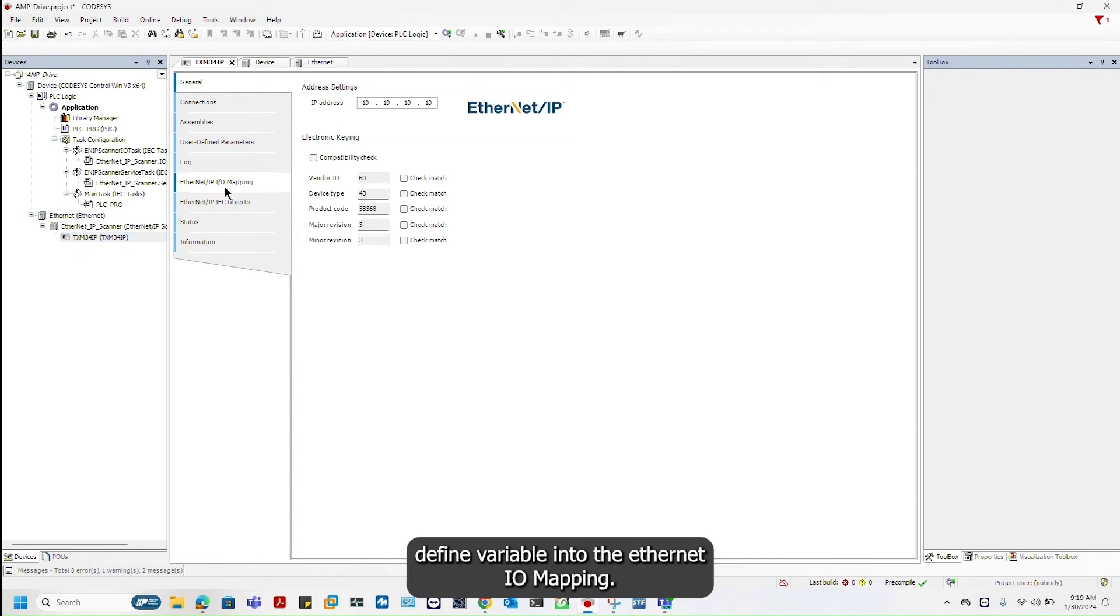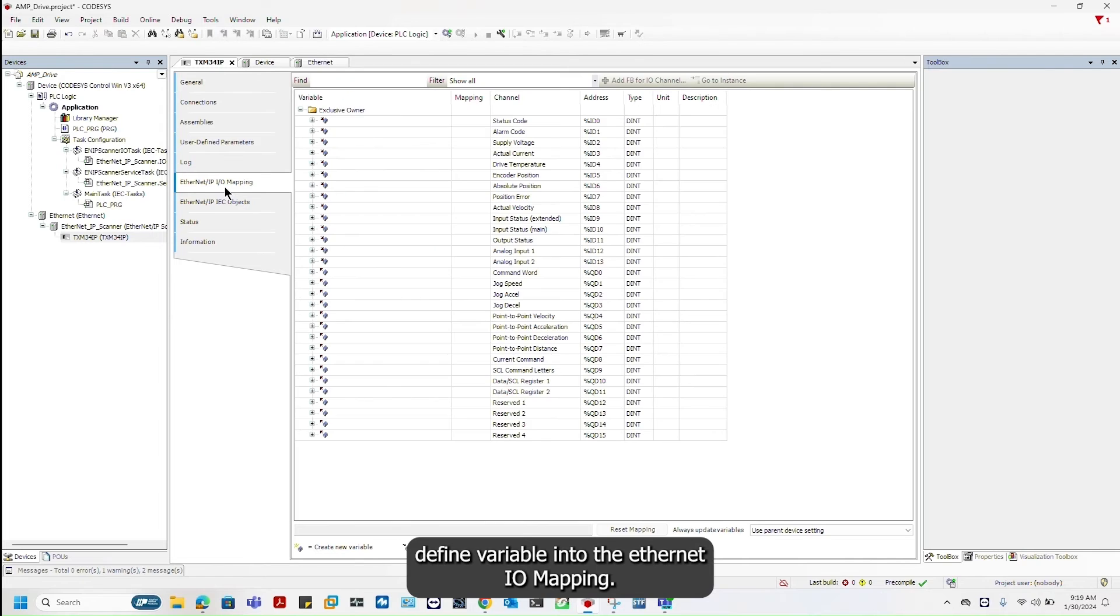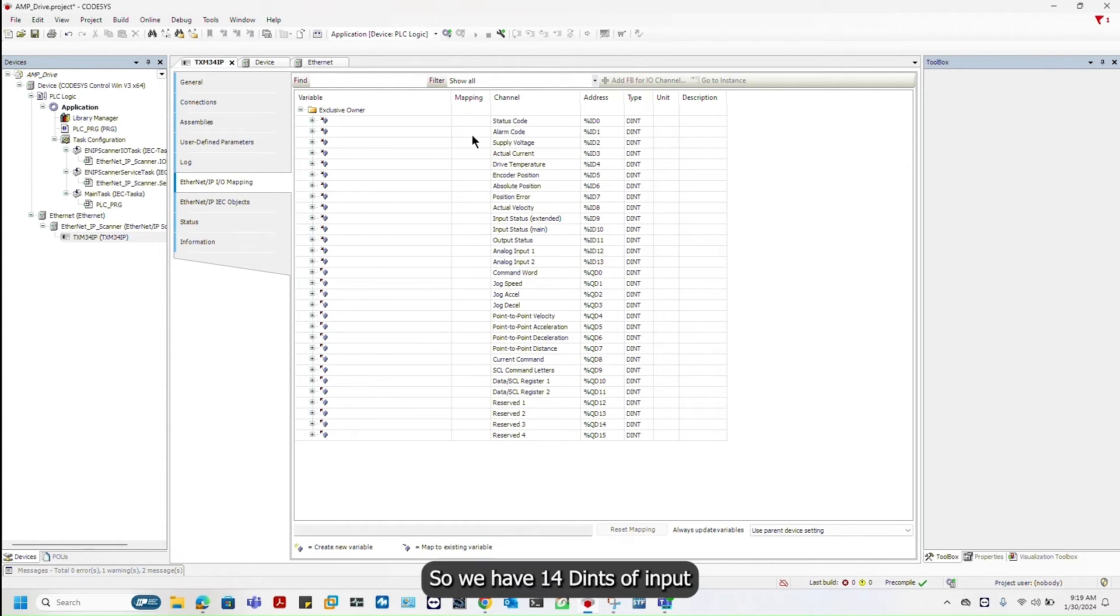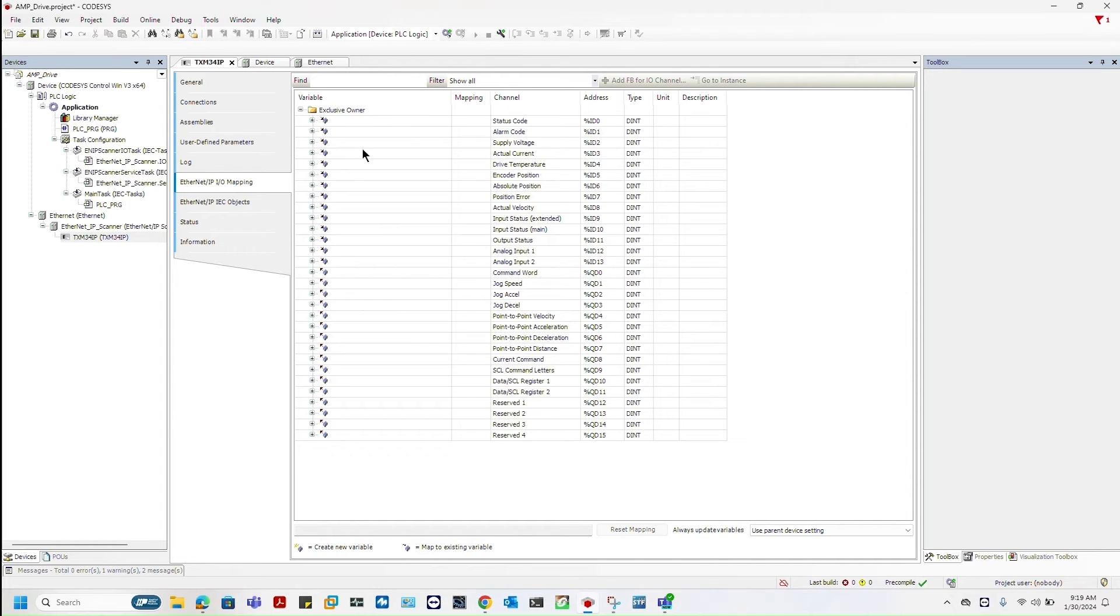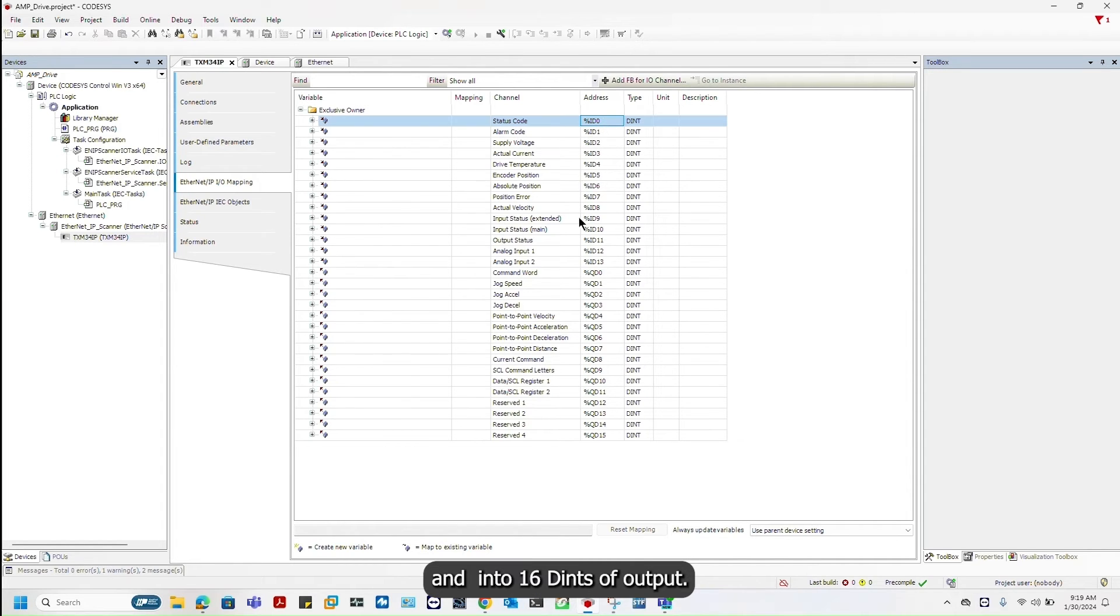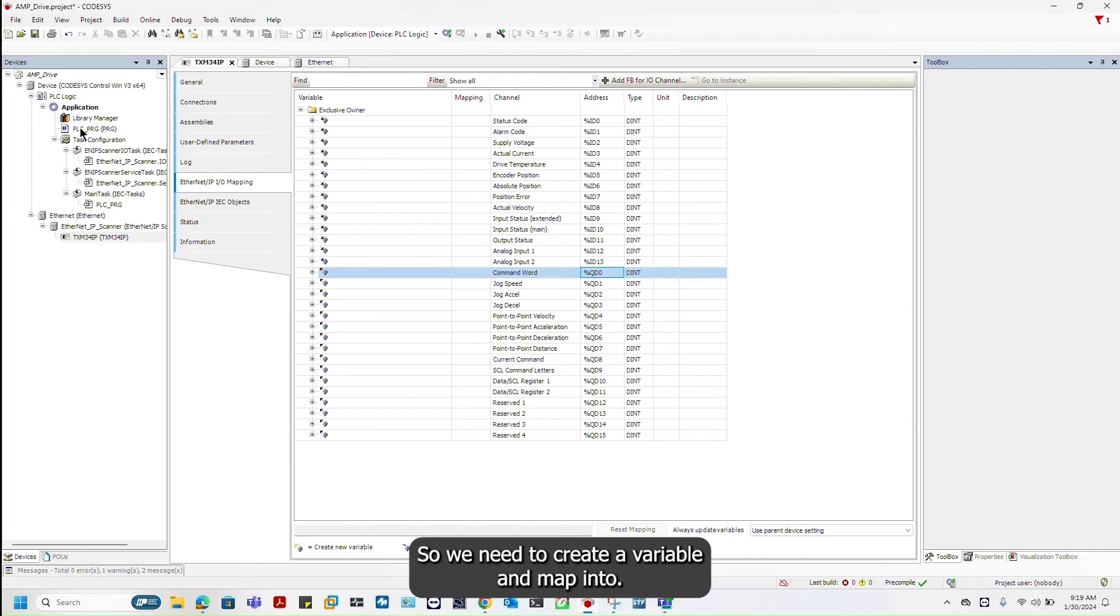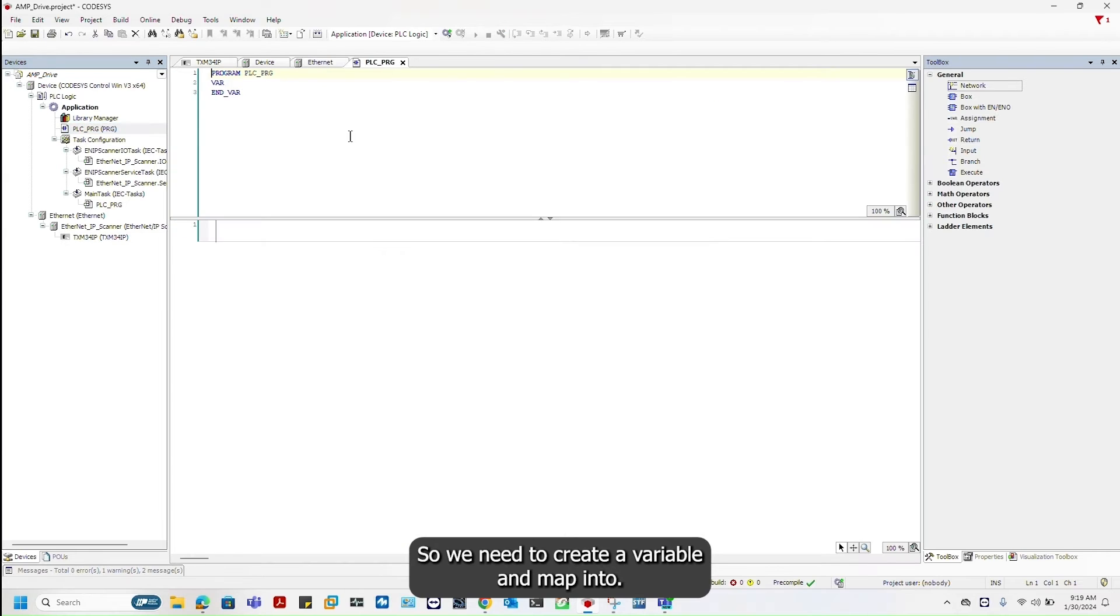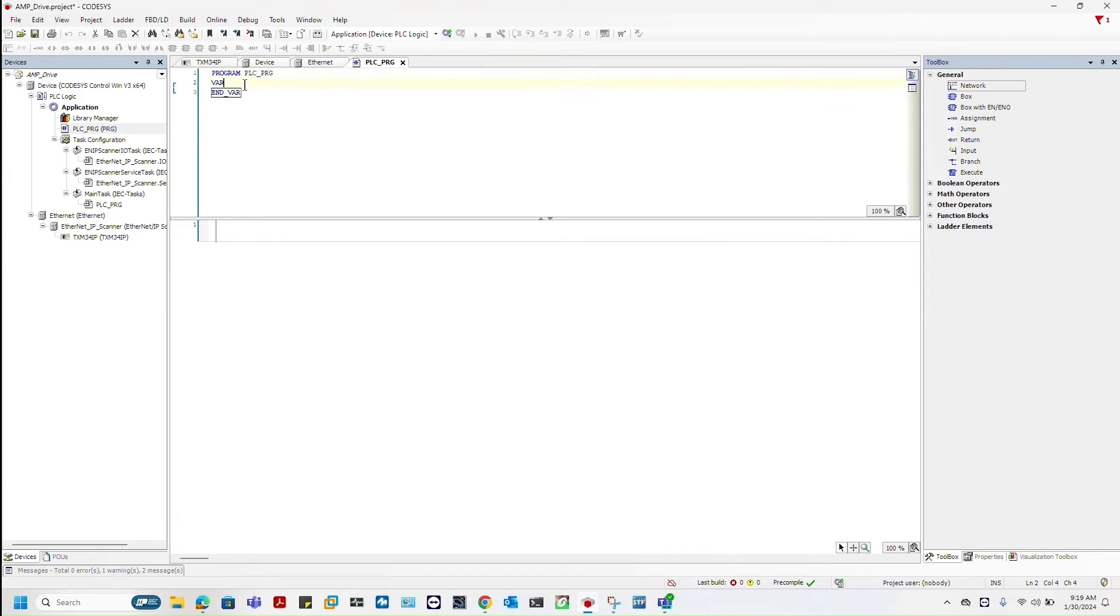Now let's define variable into the Ethernet IOMapping. We have 14 DINTs of input and 16 DINTs of output. We need to create a variable and map into.